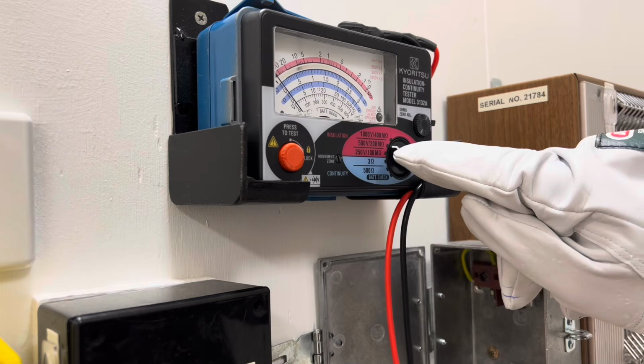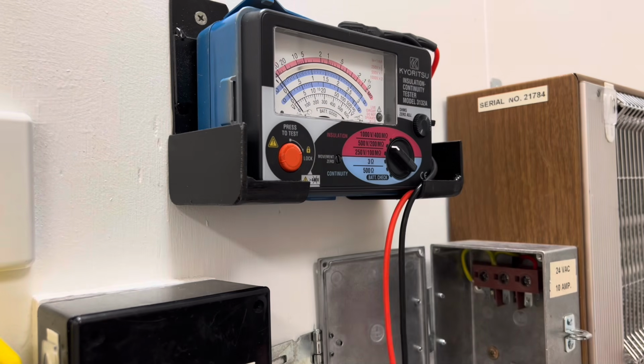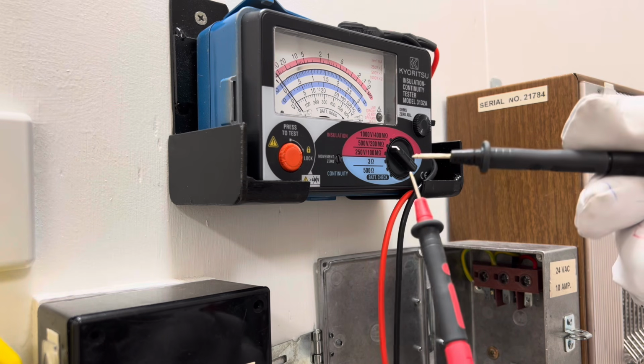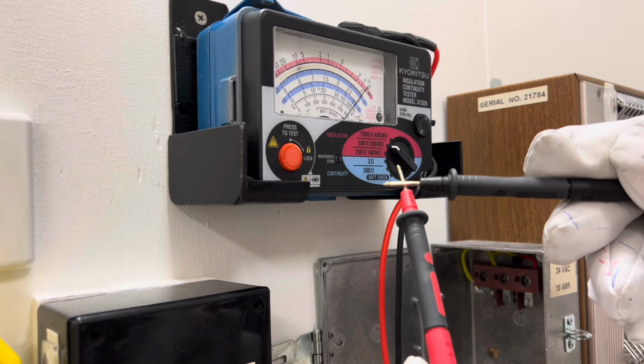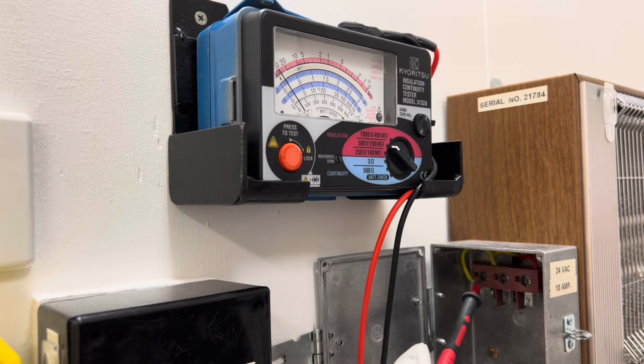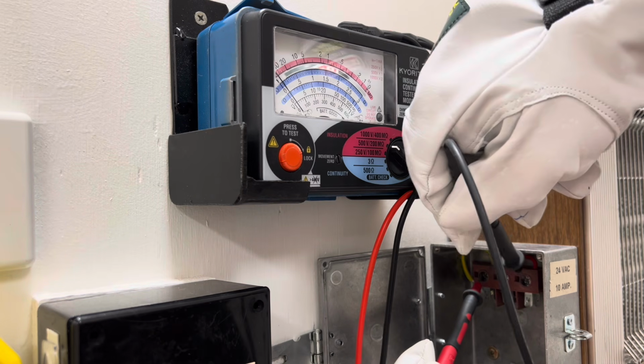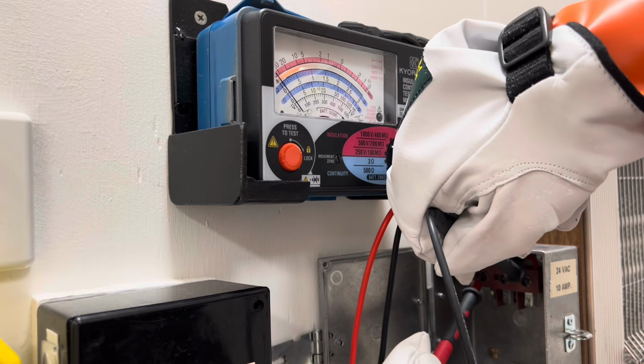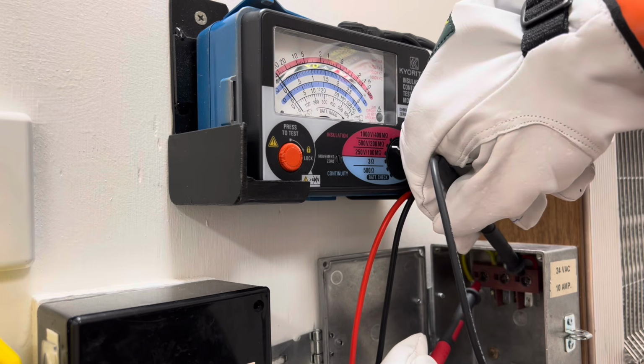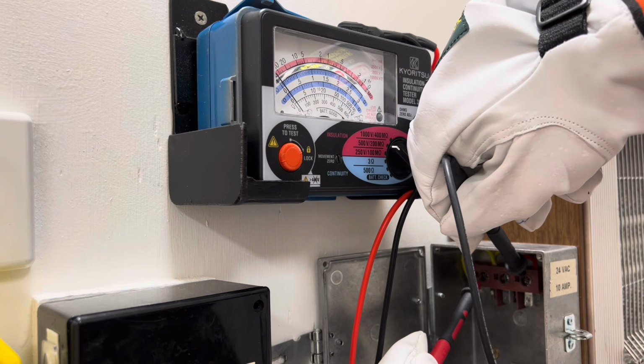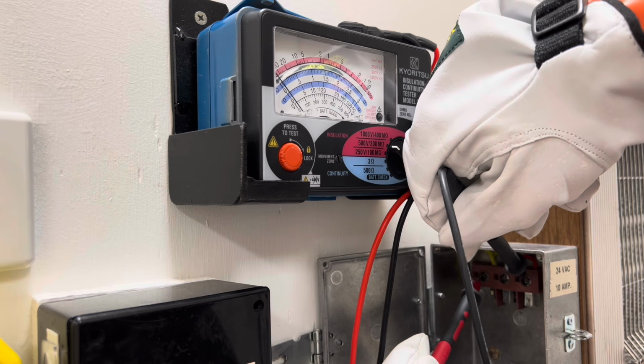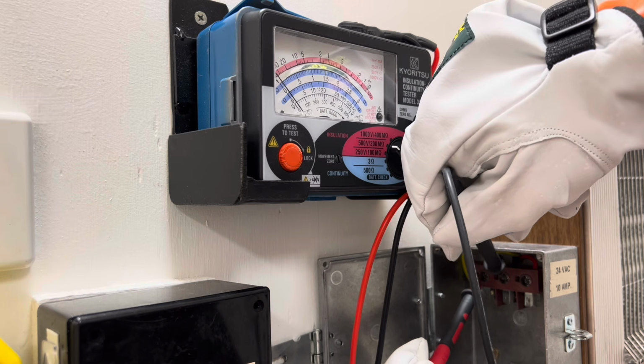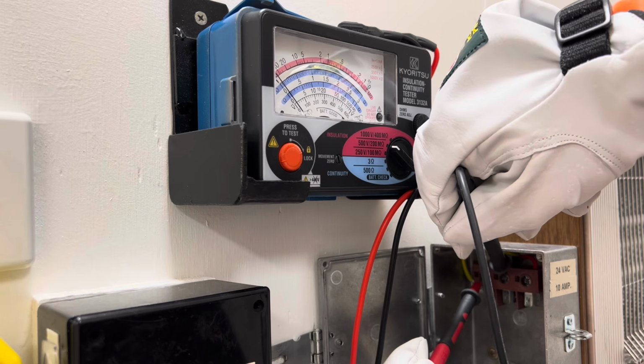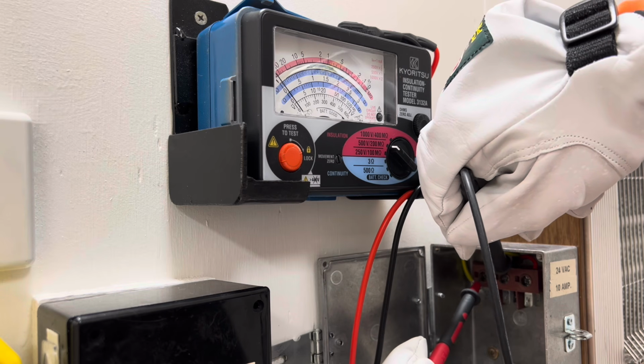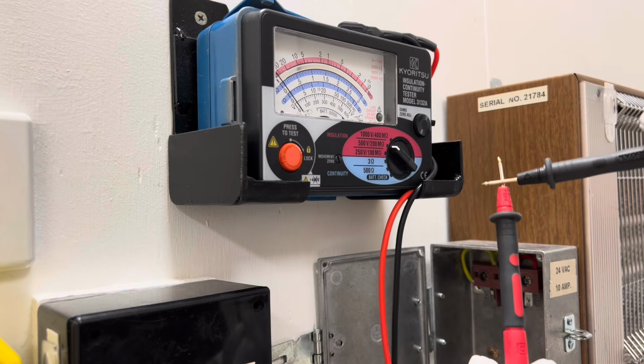We set our IR tester to 500 volts scale, which is double the voltage of the appliance. Short our leads up to make sure our meter's working. And then we can test from the earth terminal to the active terminal. And we have a reading of greater than 200 megohm, which is excellent for this. And from the neutral terminal to the earth terminal, which is also greater than 200 megohm.